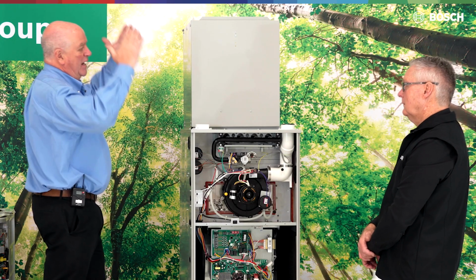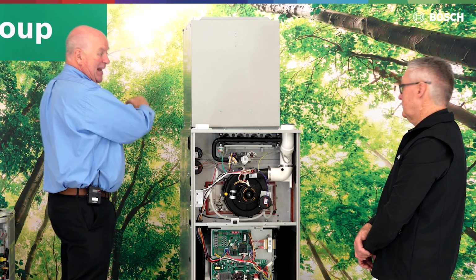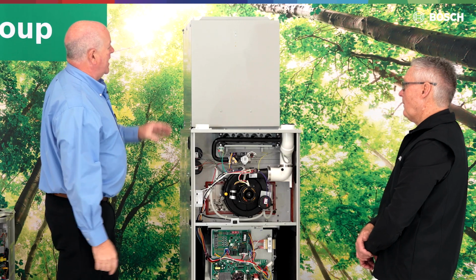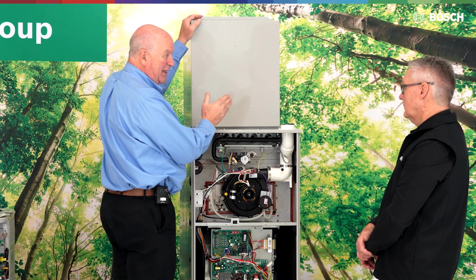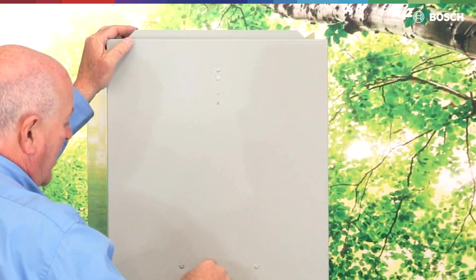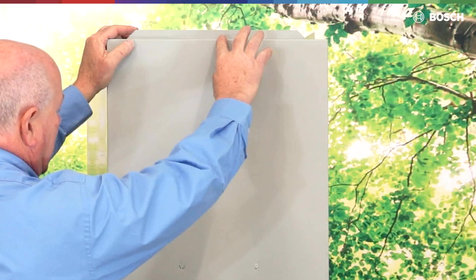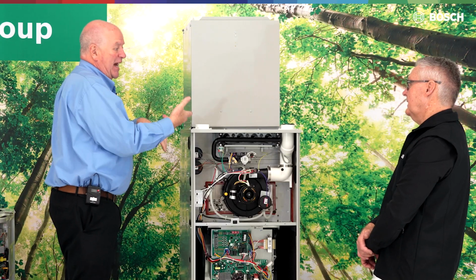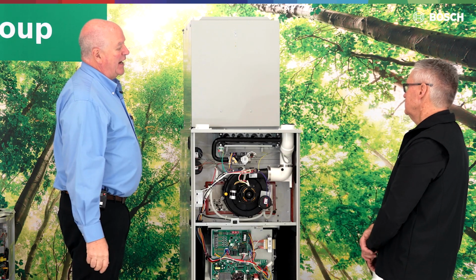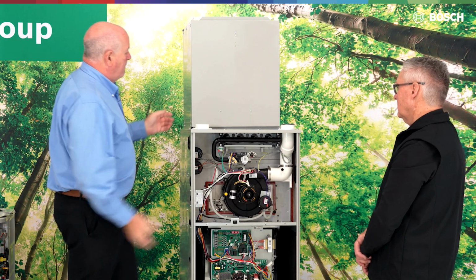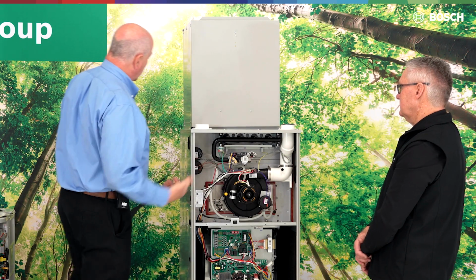If you're in a knee wall in an attic, you may not be able to get out the back. So guys and gals, I don't think this is in the manual, but if you want to make that conversion, you'll require 4 additional holes - measure down, get this one, then you can actually flip that coil around inside the box, and you've got that now for left-hand or right-hand, base on flange. Wow, that's awesome. Let's turn it back around.